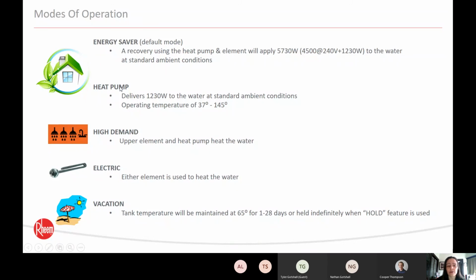So what is the recovery on a heat pump? If we're in heat pump only mode, it delivers on the low end about 1,200 watts of recovery. On the high end, closer to 1,800 or 2,000 watts of recovery. That's typically based off of the humidity and the temperature of the air, so that'll fluctuate a little bit. But on the low end, 1,200 watts of recovery. So again, a little bit lower recovery, but you can run in heat pump only mode.